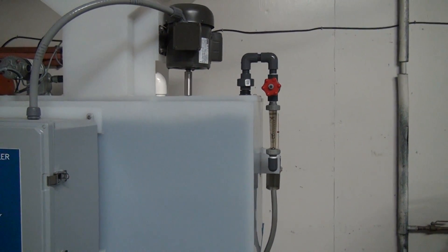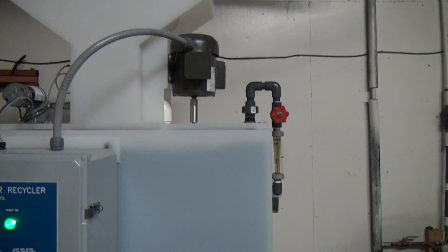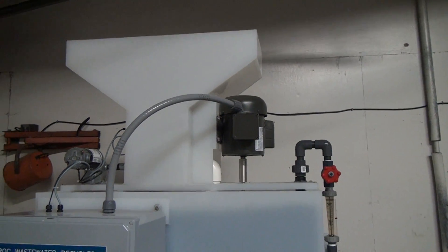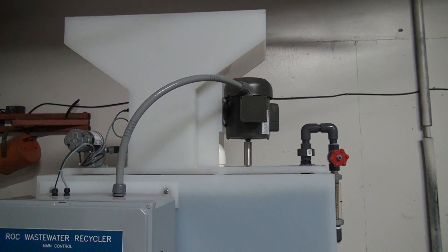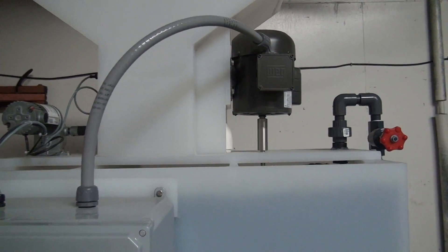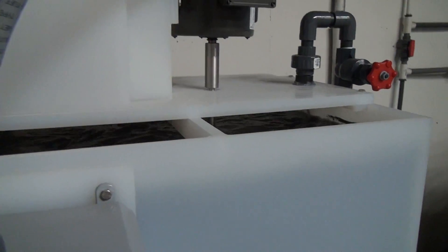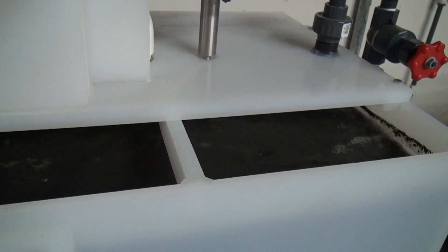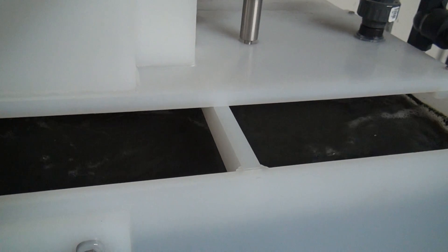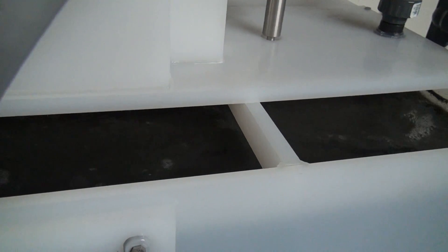The water is agitated with a mixer. The hopper on top holds 100 pounds of water treatment chemicals, which is a powdered flocculant powder. It's metered into the water and agitated, causing a flocculation process. This is where all your metals and contaminants are treated out of your water.